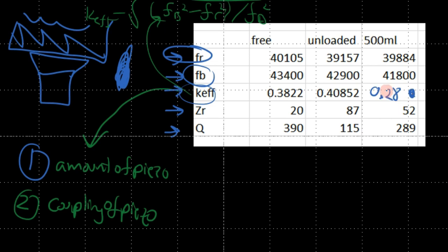So we have this significant drop. And what's the significance of this drop? Why does it drop? It's because there's a lot of inactive material. Okay, there's a lot of inactive material, and it is reducing the coupling. And is that a bad thing? No, it's a good thing. It's a good thing to see this. And the reason it's a good thing to see this is because we know that our piezoelectric material is coupling with the outside. But in terms of coupling with the outside, it reduces the relative amount of piezoelectric material.